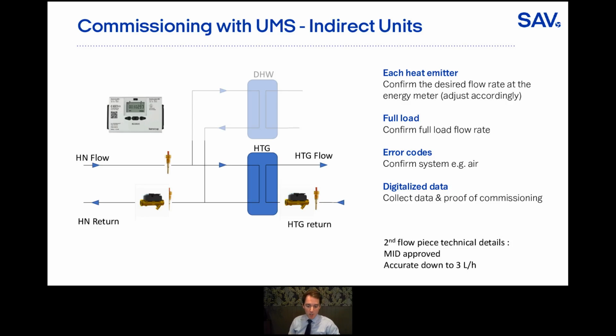This is where the UMS comes into it. So you already have an energy meter there through the metering and billing regs. That energy meter can then take in that second flow piece and a third temperature sensor. You now have visibility onto that secondary side. You can now do the same commissioning process that we would do on the direct units. So assuming you've got the pressure independent control valves on your radiators, you can set each separate heat emitter to the right flow rate, and you can verify it on the energy meter, saving time on site.